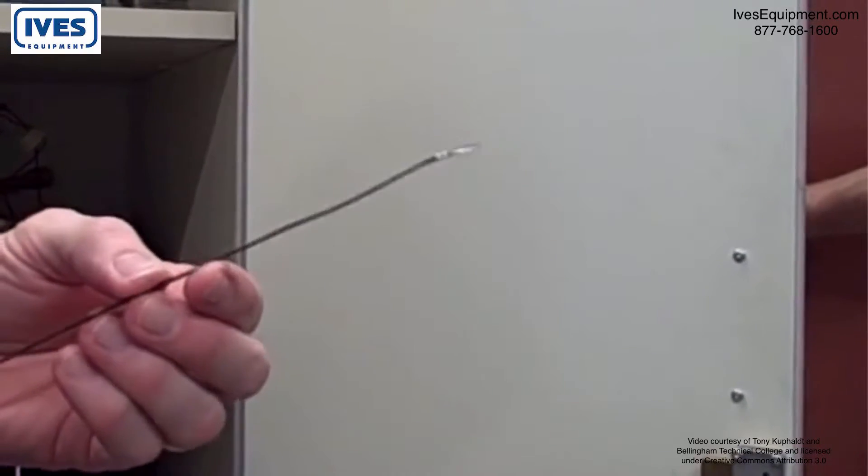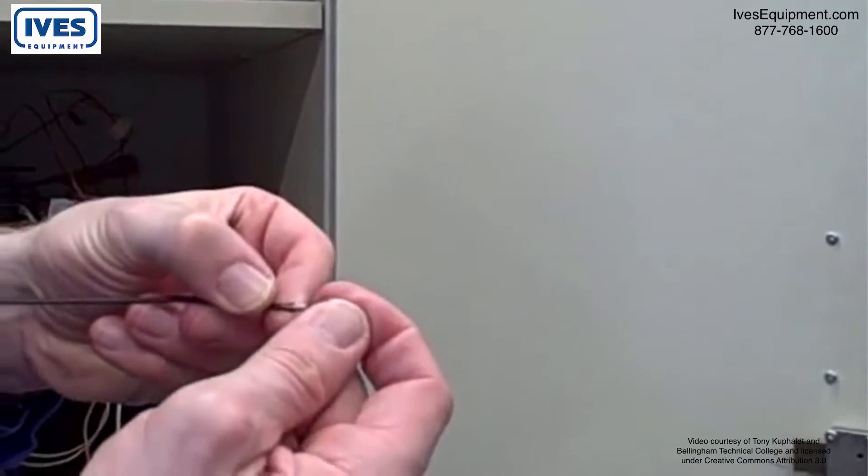This right here is thermocouple grade wire. You can tell that from the brown sheath. And if we simply took these two wires here and twisted them together or spot welded them or otherwise clamped them or silver soldered, that itself would form a thermocouple junction.